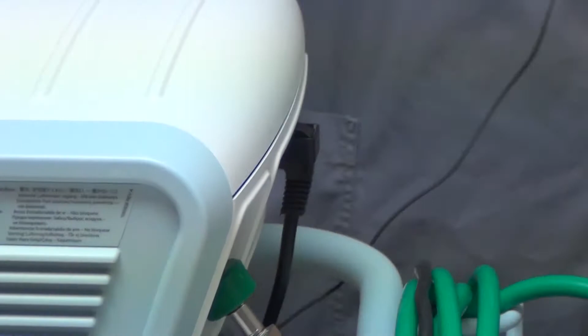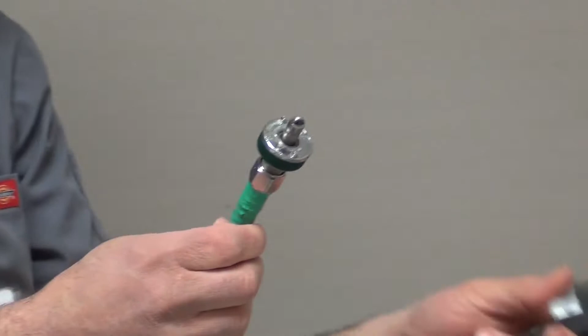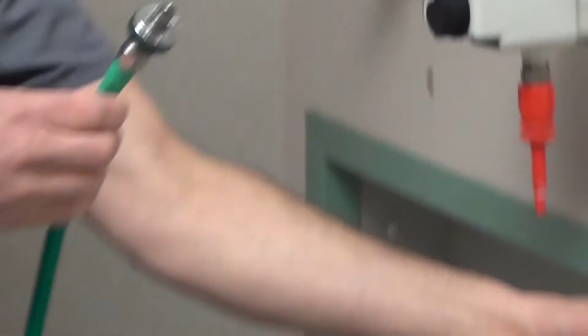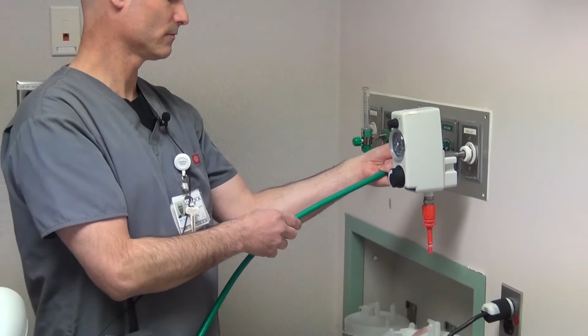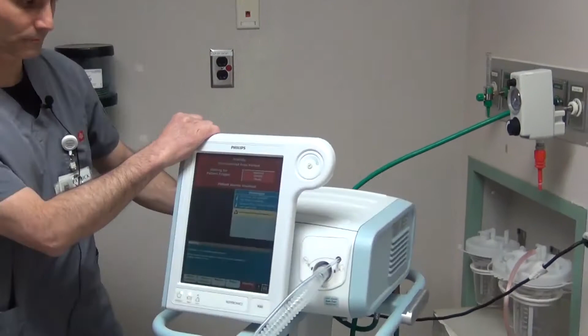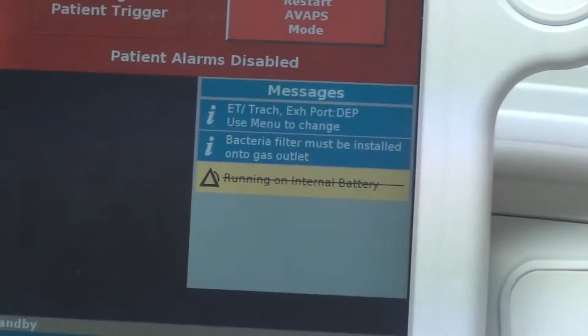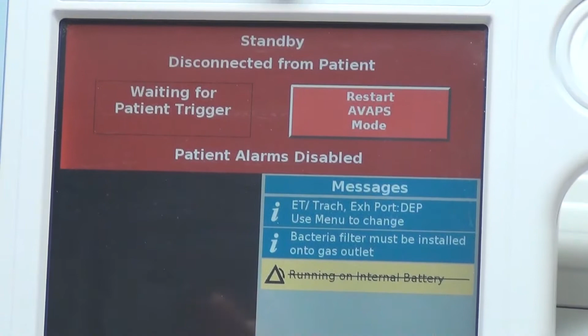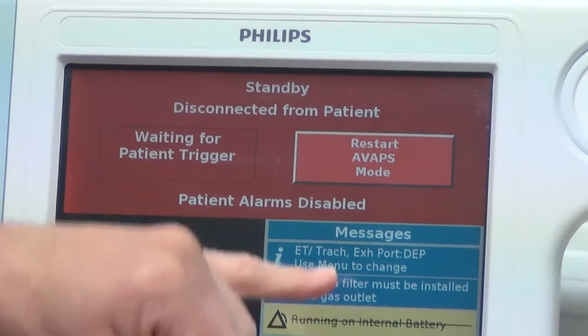So I'm going to spin it around here to show you the back. We have the oxygen tubing and we have the power cord. We're going to plug those into the wall. Go back to the front of the machine here. Notice it crossed off running on internal battery. That's because the machine sensed it was plugged in. So if you are going to be using these machines and you make a little mistake like that, the machine will tell you in this little message board what's going on.